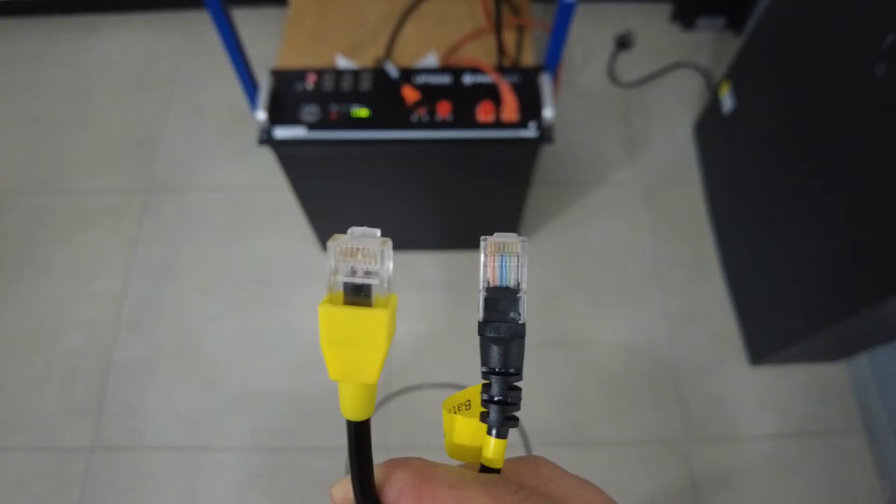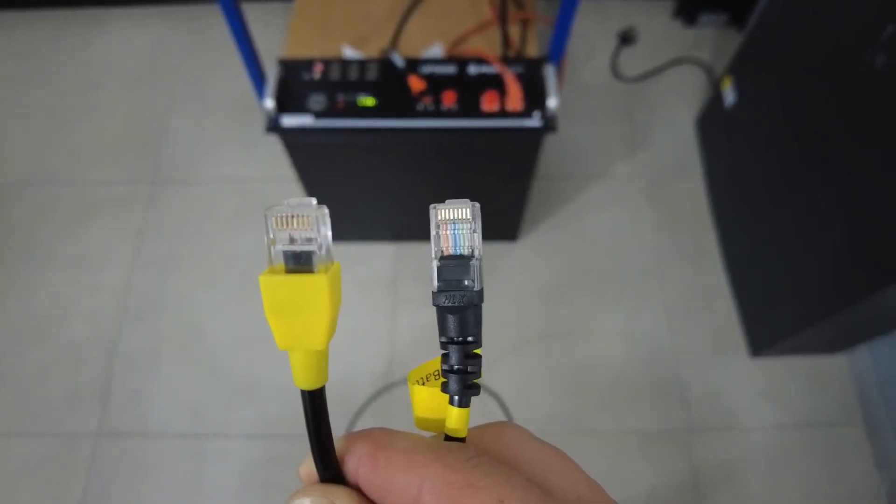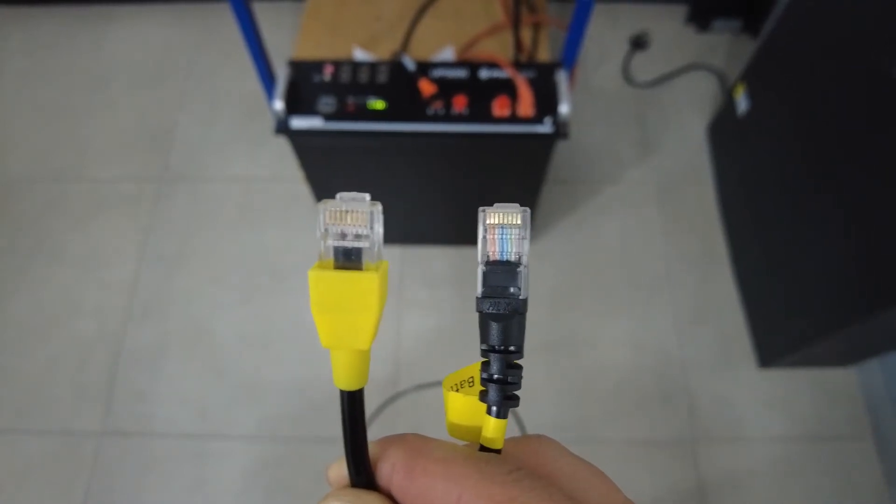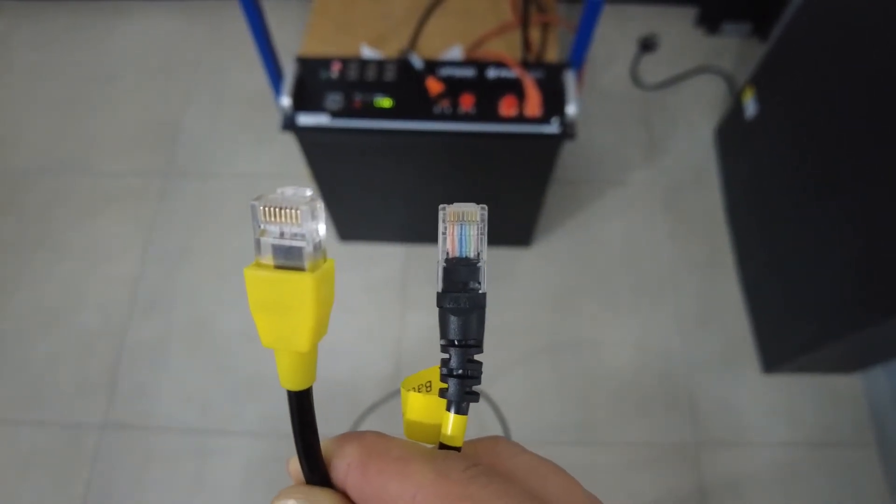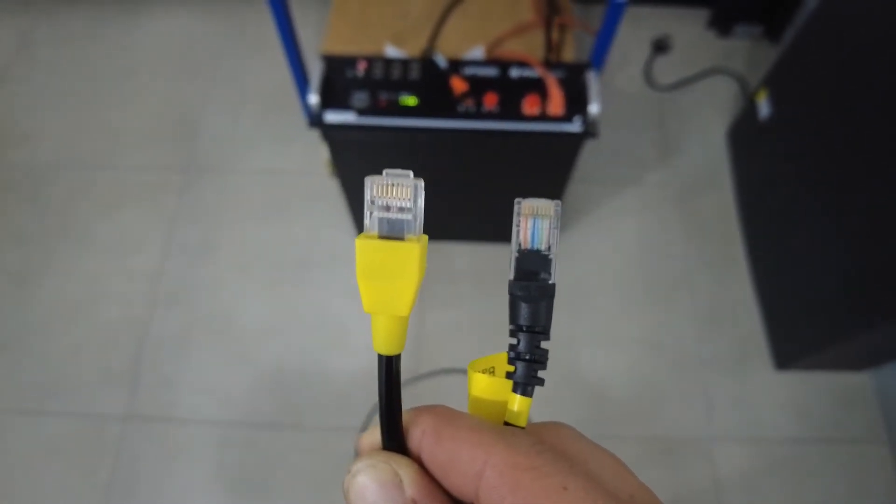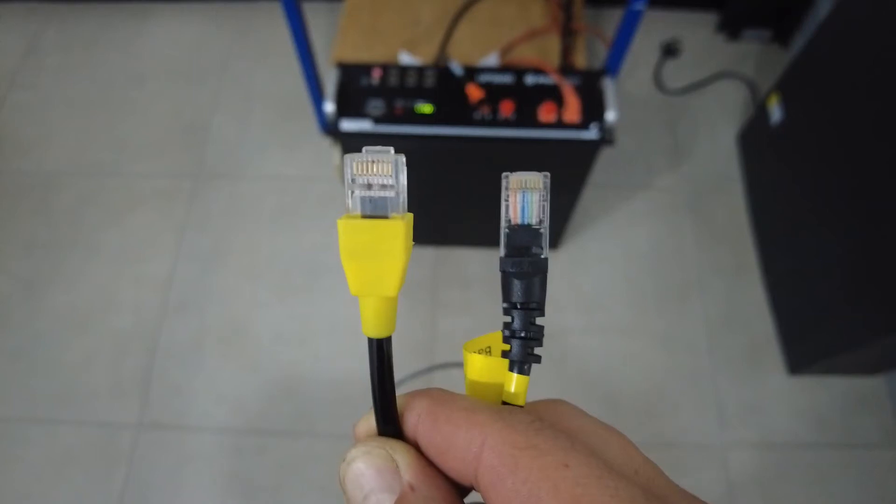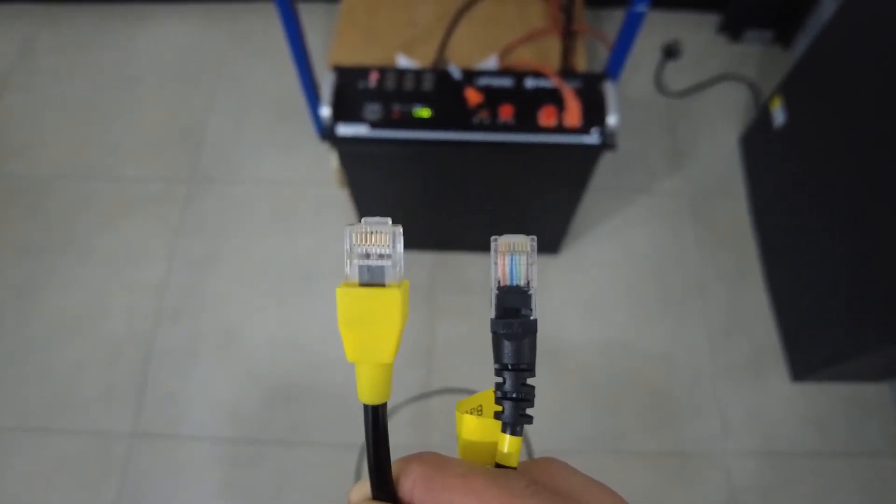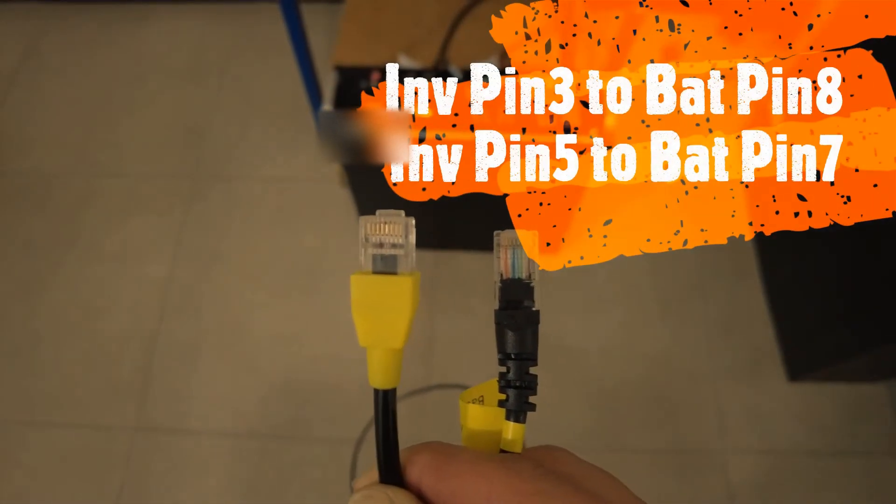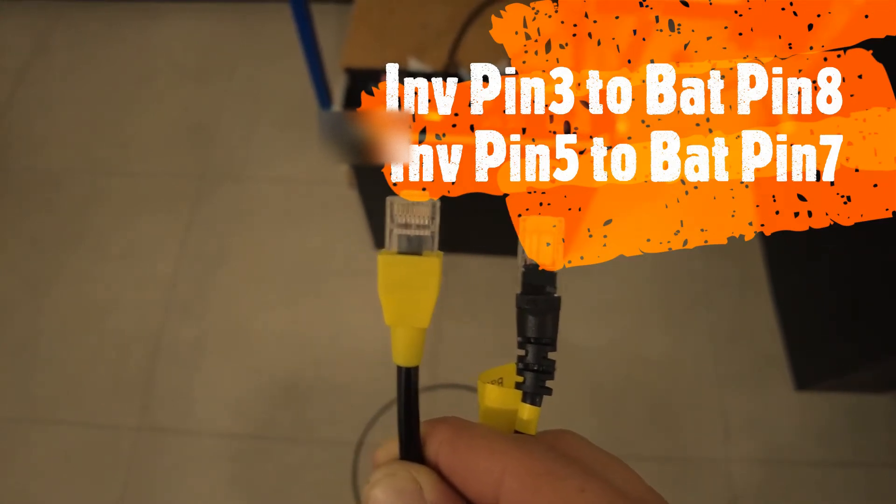For the correct BMS communication pinouts, you can use a normal networking cable with the normal color coding scheme on the battery side, and then refit a new plug on the inverter side with the correct wiring to get your communication up and running. In this case, on the inverter side, pin number three will lead to battery side pin number eight, and inverter side pin number five will lead to battery side pin number seven.